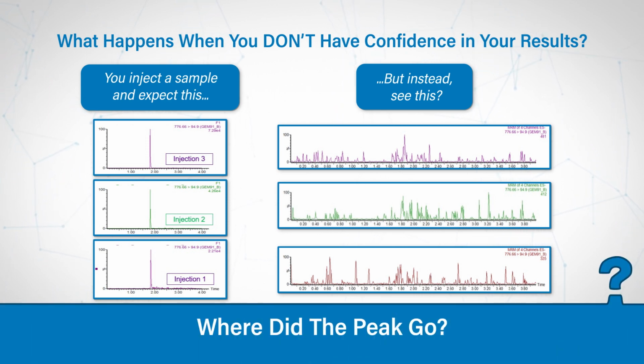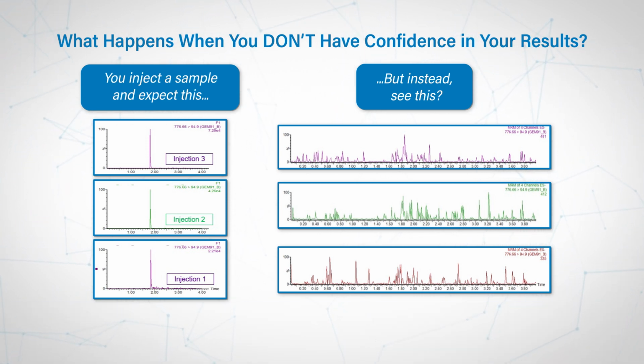Like, what happened? I mean, it could be a lot of things. It could be non-specific adsorption. It could be some kind of metal interaction, which has been more publicized lately, especially in a lot of peer-reviewed papers. So it could be one of those two things. Well, I know certain analyte classes can have this type of chelation or non-specific adsorption to metal ions within the flow path. Things like phosphorylated, carboxylated. Those analytes really come to mind when I think about sticking or, again, adsorbing to those metals within the flow.